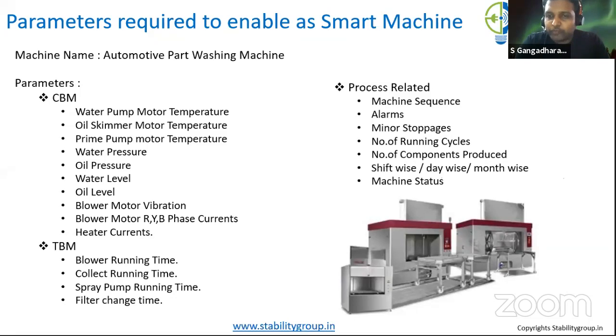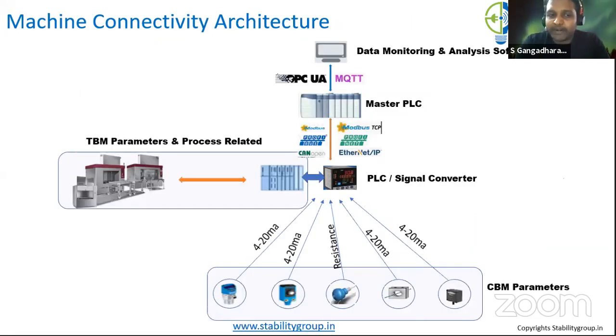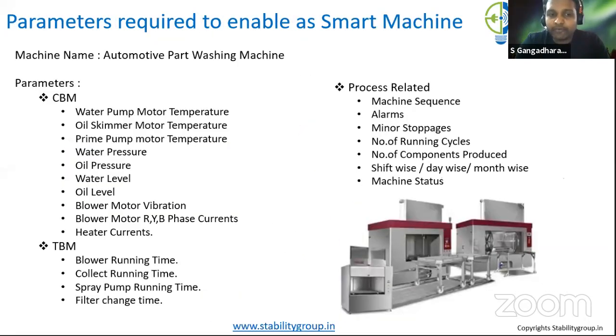It also gives a forecast so the machine can predict failure before it happens. The customer is happy because he can find out if there is any vibration happening - you can do fast Fourier transform analysis on the vibration. That's a very good technique.